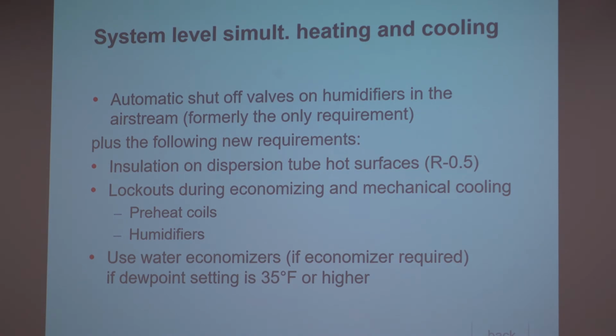So one of the things that the standard 90.1, and I believe IECC is almost the same as this, requires is that you have some sort of method of eliminating simultaneous heating and cooling. 90.1 went a little bit further and said that we don't want you to have humidifiers in the airstream that are unintentionally adding heat to something that you just cooled. And so there are some limits on almost accidental or incidental simultaneous heating and cooling at the central unit. So that's what that is there.